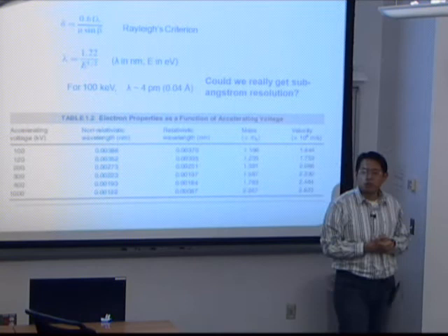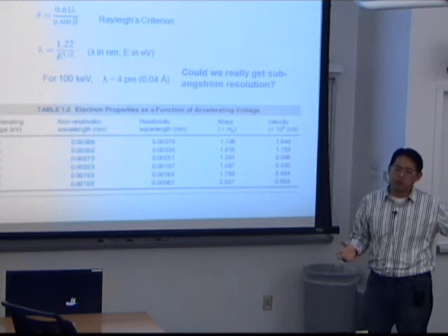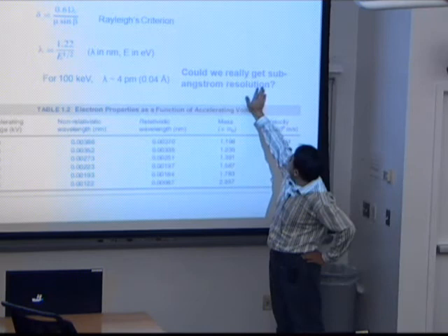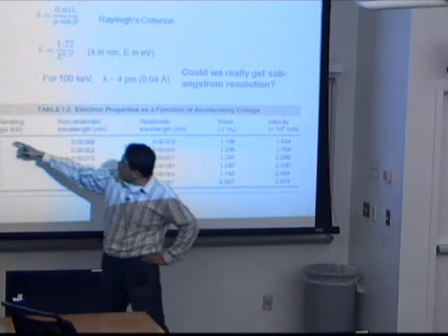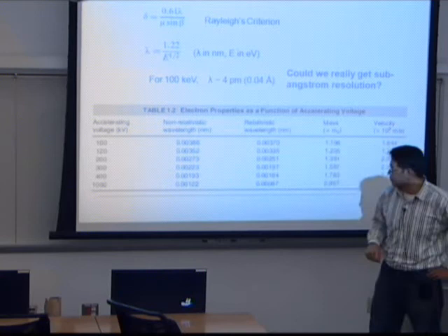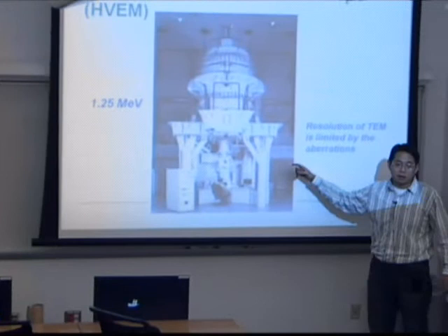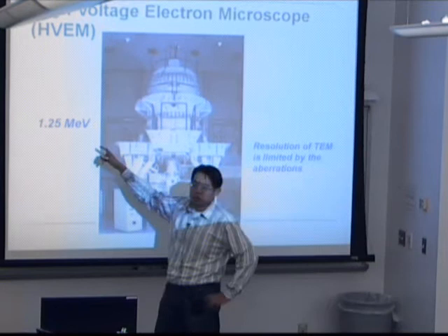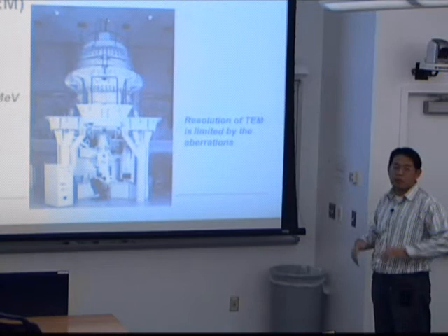But could we actually get sub-Angstrom resolution? It's very hard, and we are still working on getting resolution closer to one Angstrom. The machine downstairs has two Angstrom resolution; another has 1.4 Angstrom resolution. We cannot get sub-Angstrom resolution even with very small electron wavelength. We can go from 100 kV to 1 MeV (1000 kV) and get a wavelength of 0.01 Angstrom, but we still don't see a lot of improvement in resolution. I'll show you the very high voltage electron microscopy built by JEOL in Japan — three floors high, generating electron energy of 1.25 MeV — but the resolution has not improved to sub-Angstrom.